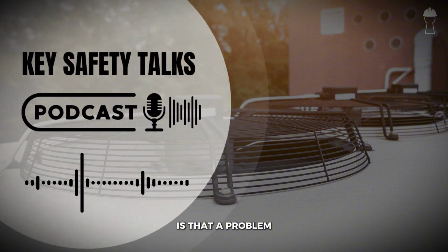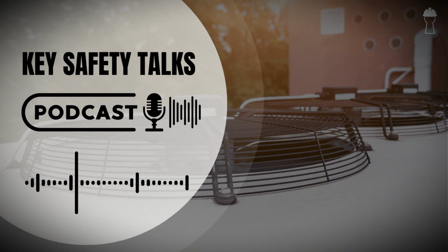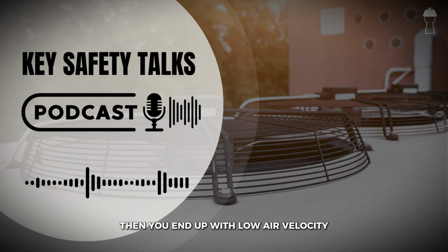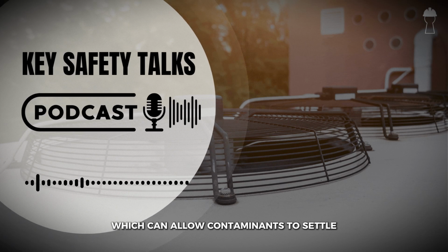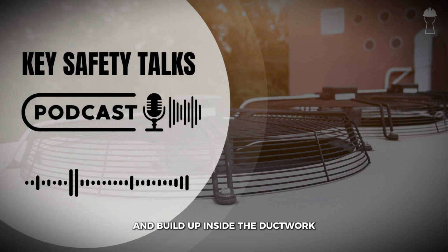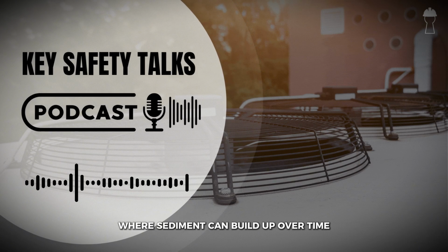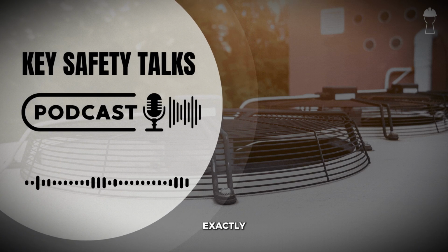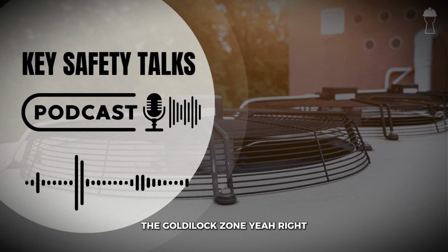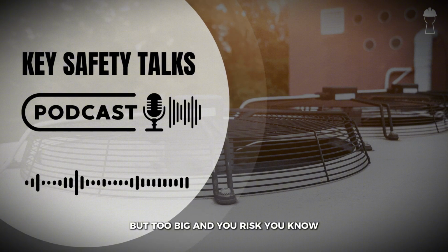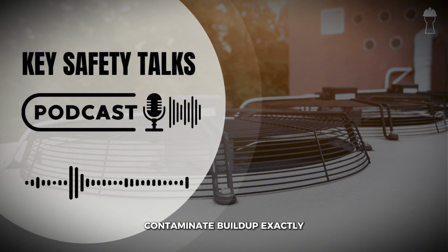Is that a problem? Yes, it can be. If the duct is too large, then you end up with low air velocity, which can allow contaminants to settle and build up inside the ductwork. It's like having a slow-moving river where sediment can build up over time. Exactly. So it's really all about finding that sweet spot. The Goldilocks zone. Yeah, right. Too small, you restrict the airflow, but too big, and you risk contaminant buildup.